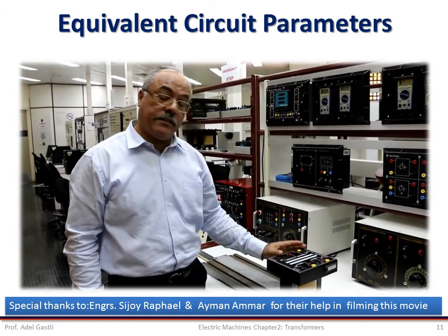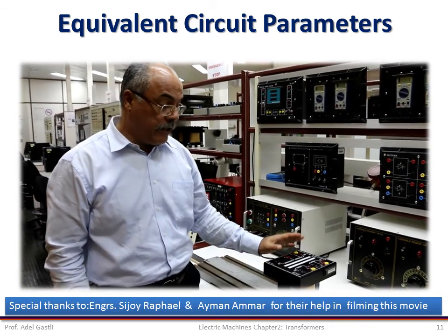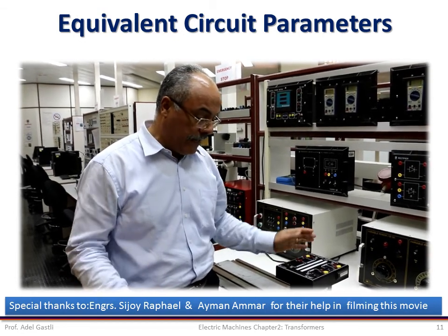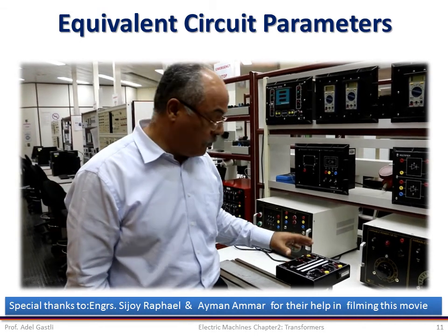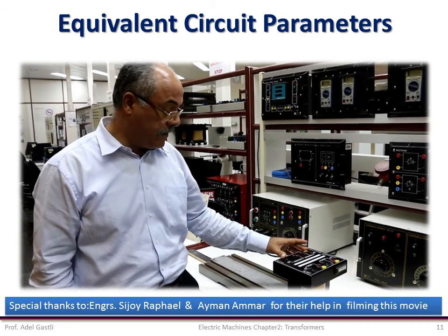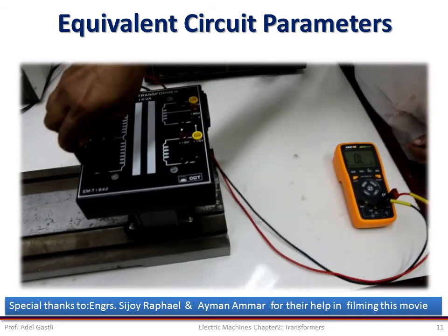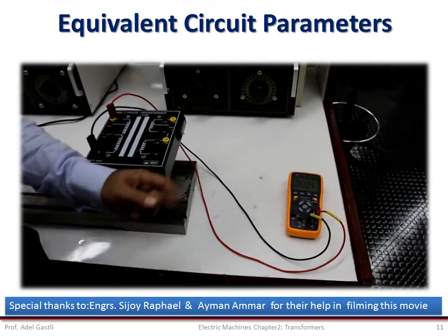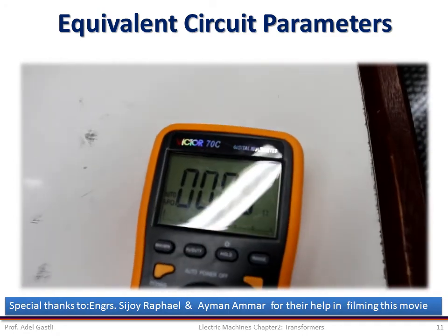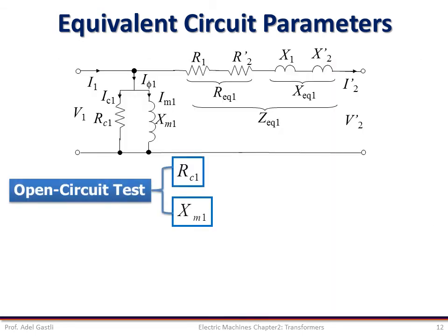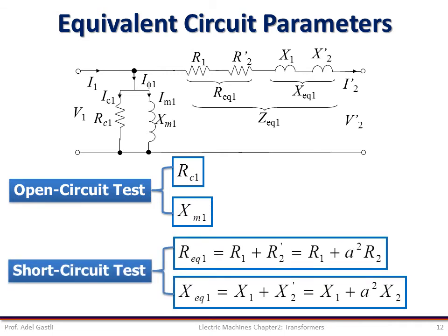Note that both methods should give the same results. After doing the open circuit test and the short circuit test, there is one more measurement needed to complete all measurements for finding all equivalent circuit parameters. The next measurement is to measure the primary winding resistance R1. For that we use a normal ohmmeter, connect it to the terminals of the primary winding, and take the readings of the resistance. After calculating RC1 and XM1 from the open circuit test and R_equivalent1 and X_equivalent1 from the short circuit test, we can deduce the other equivalent circuit parameters R1, R2, X1, and X2.